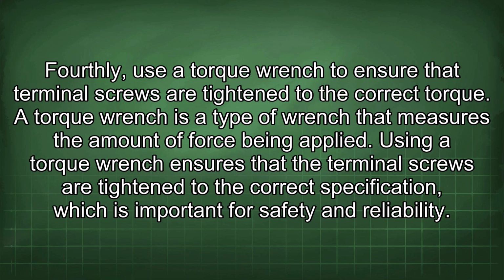Fourthly, use a torque wrench to ensure that terminal screws are tightened to the correct torque. A torque wrench is a type of wrench that measures the amount of force being applied. Using a torque wrench ensures that the terminal screws are tightened to the correct specification, which is important for safety and reliability.